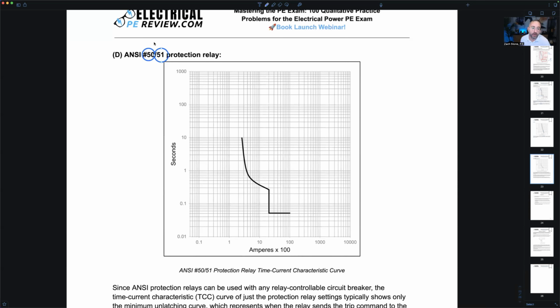my desk behind there, we had to use these together in tandem, and we could wire their trip signals in parallel so that either the instantaneous could trip the breaker or the overcurrent could trip it. Nowadays, our relays, I think that's also a differential up there on that bookshelf. That's a modern one, right? Microprocessor based. Nowadays, it's pretty much a computer, and we're telling the computer when to trip. So instead of having multiple relays for a combined function, now we have one relay that can do it all.